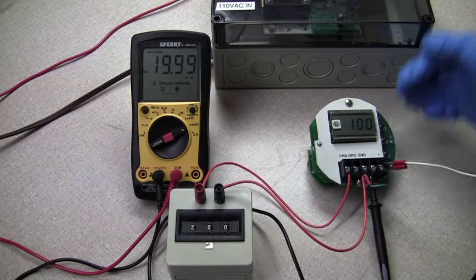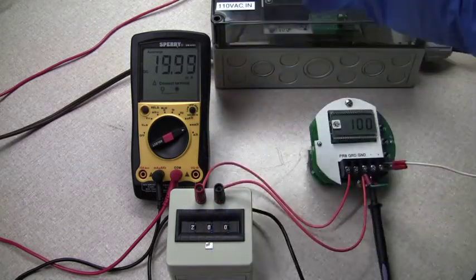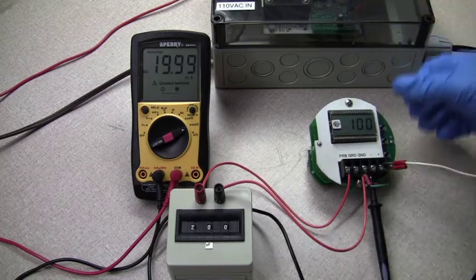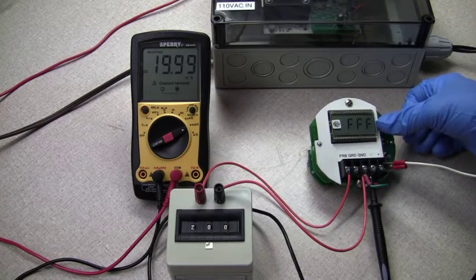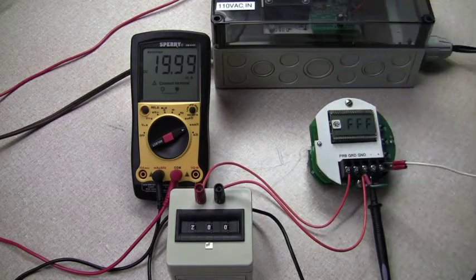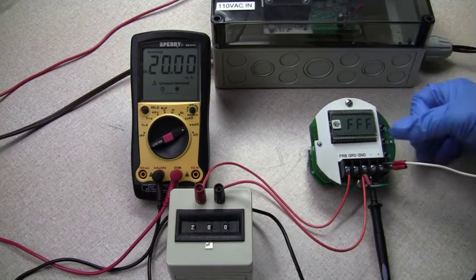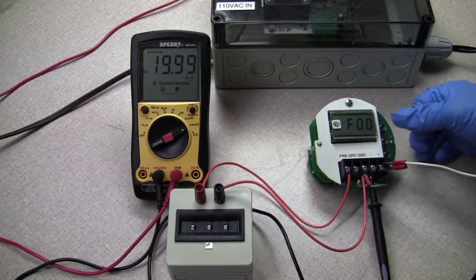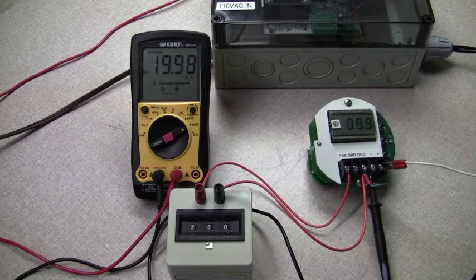You will raise the level of liquid in your tank in the field to your desired high set point. Then you hit the SW1 button. FFF means you're setting your full. SW3 enters.